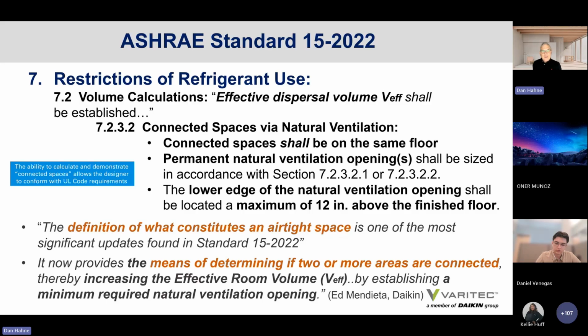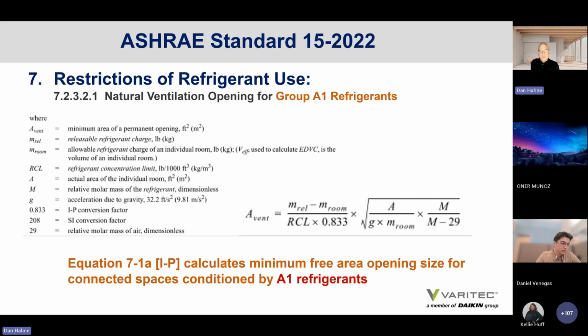According to Ed Mendieta of Daikin, the definition of what constitutes an airtight space is one of the most significant updates found in Standard 15. What can be defined as a connected space increases the overall volume of the effective dispersal volume of a space. He goes on to say that the standard now provides the means of determining if two or more areas are connected, thereby increasing the effective room volume by establishing a minimum required natural ventilation opening.